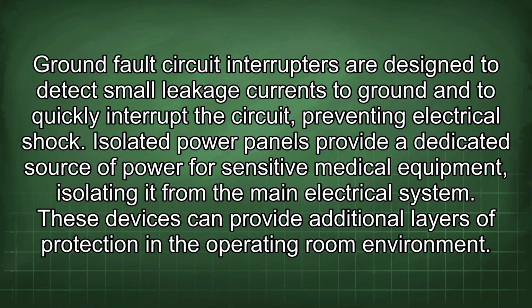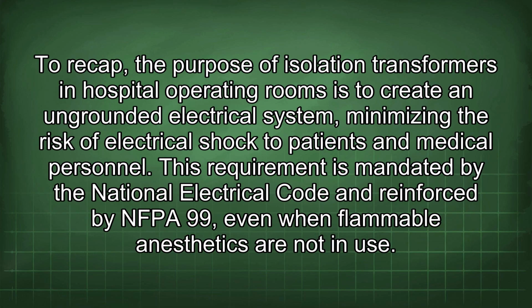These devices can provide additional layers of protection in the operating room environment. To recap, the purpose of isolation transformers in hospital operating rooms is to create an ungrounded electrical system, minimizing the risk of electrical shock to patients and medical personnel. This requirement is mandated by the National Electrical Code and reinforced by NFPA 99, even when flammable anesthetics are not in use.